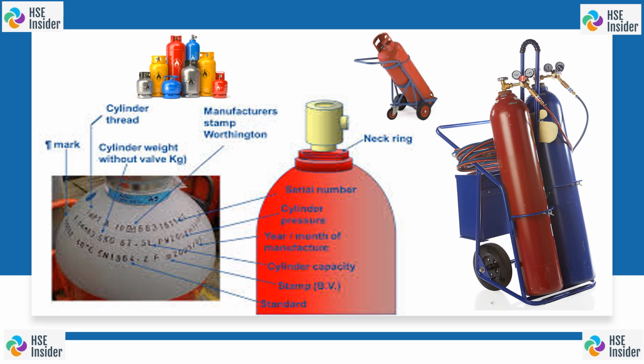In case of medical gas cylinders, the valve should meet the requirement of IS 3745. And for cylinders used with breathing apparatus, it should meet the requirement of Indian Standard 7302. So please remember these Indian Standards when you are doing the inspection on these gas cylinders.